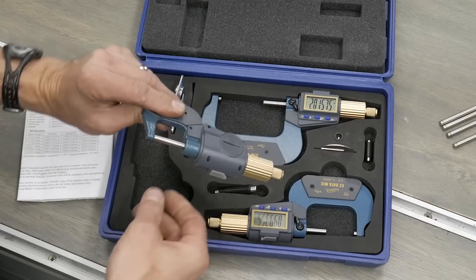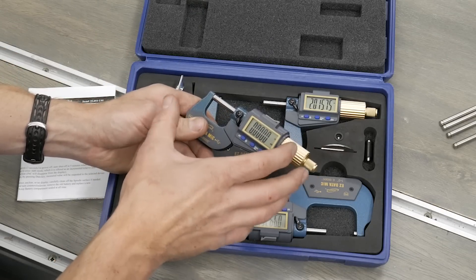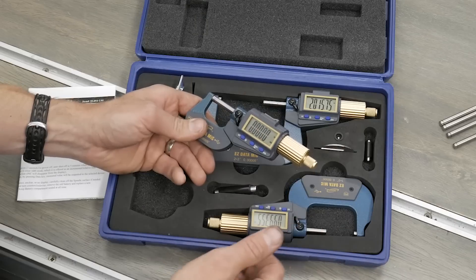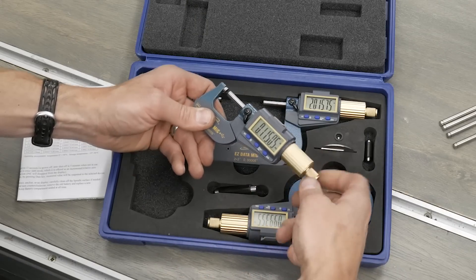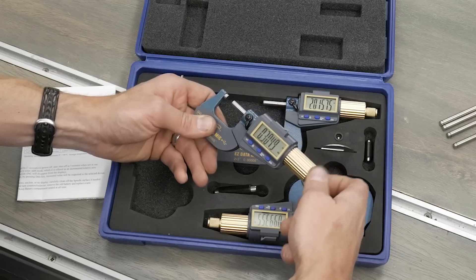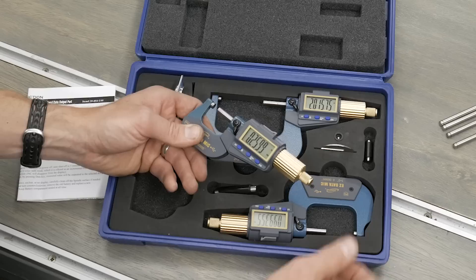So they've got an insulated frame, which is good. Keeps heat from transferring from your hand and altering the measurements based on thermal expansion, that kind of thing. And then you can do kind of a rapid traversal to open and close the measurement range with the knurled knob, which does not have the click clutch on it.